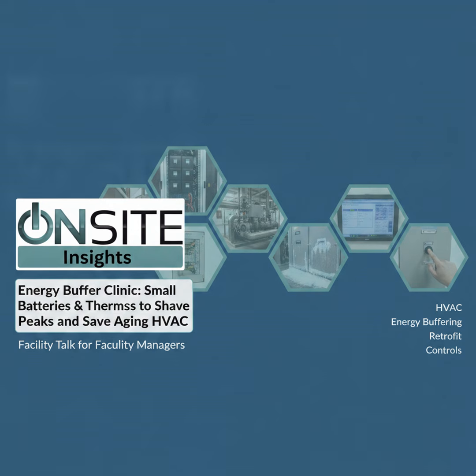Let's dig into the BMS side. What concrete logic changes keep these buffers from creating false alarms or masking real faults? Start with 3 simple rules. 1. Add short delays and hysteresis so a 1-second dip doesn't raise a high-priority alarm. 2. Monitor contactor state to detect chattering instead of immediately flagging a compressor fault. 3. Create a buffer active flag in the BMS logic that suppresses nuisance alerts while you log events. And importantly, log everything heavily during the pilot so you can tune thresholds.